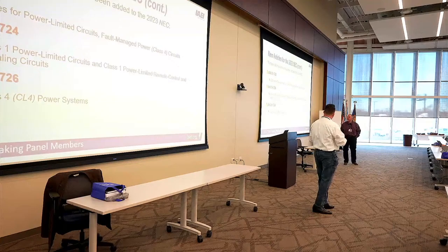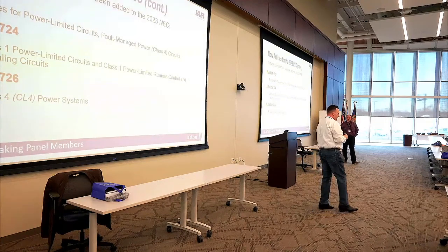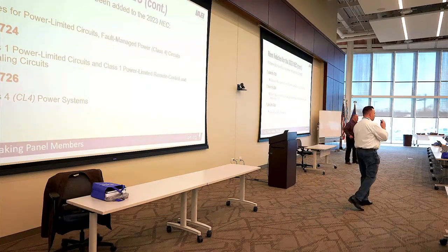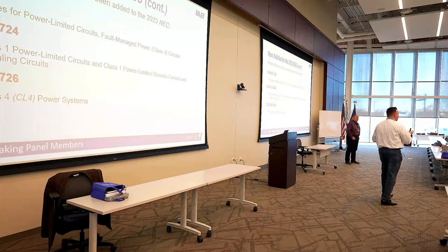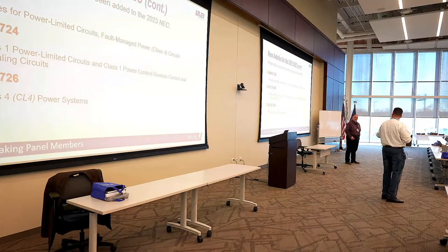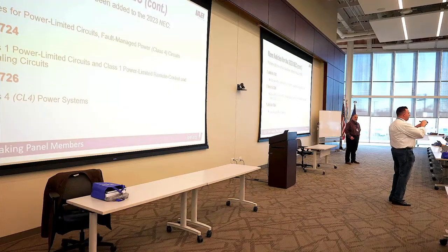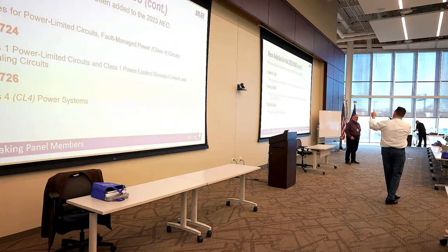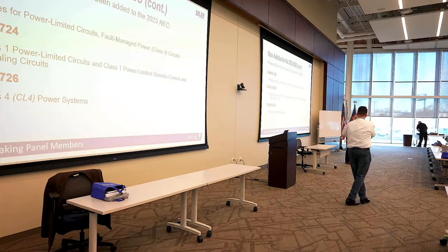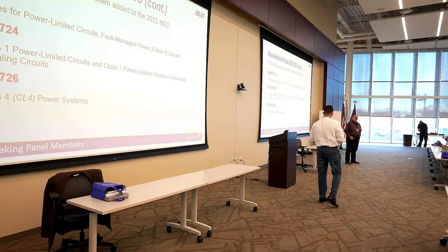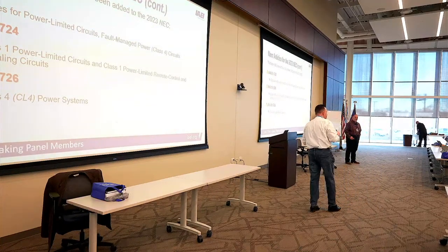I like what we did with 722, because it took the requirements out of 725 and 760 fire alarms - the general requirements for power limited circuits and fault managed power - and took the redundant requirements out of those articles and put them into one article. Now you go to one article for all of those requirements. So 722 is a great article that combined things, and it included class 4 fault managed power.